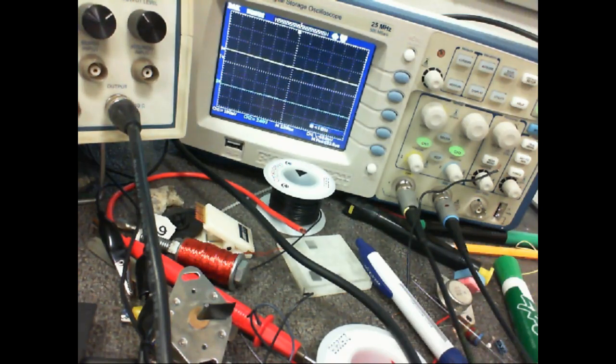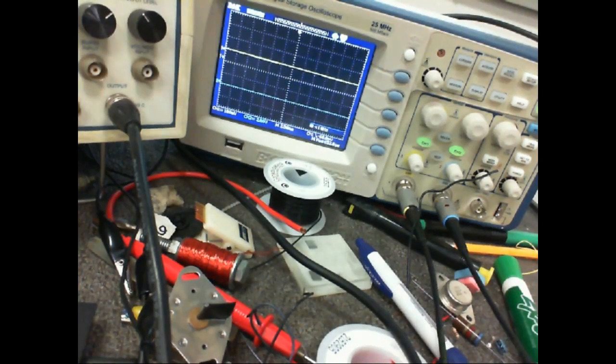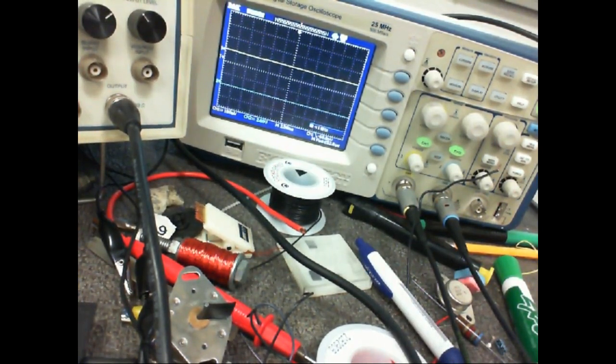So right now I'm picking this up. I'm just standing here, and I'm picking this up through what we call electromagnetic interference. So when these magnetic waves fly through my body, it induces a voltage into my body. Now the problem we have is with signal wires. We don't have problems with EMI on power wires because they're conducting a lot of current, right? It's hard for electromagnetic interference to induce something when there's a lot of current there.